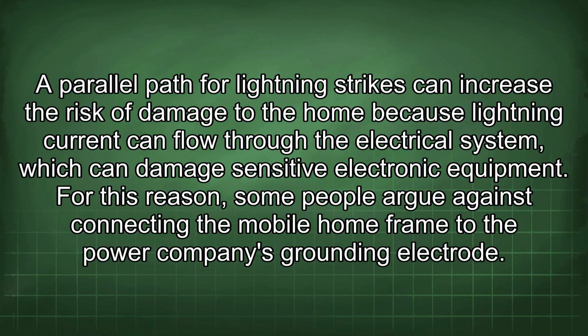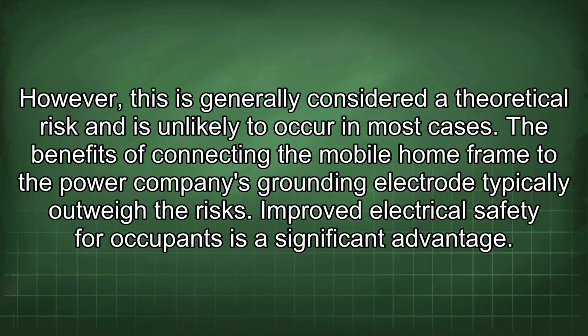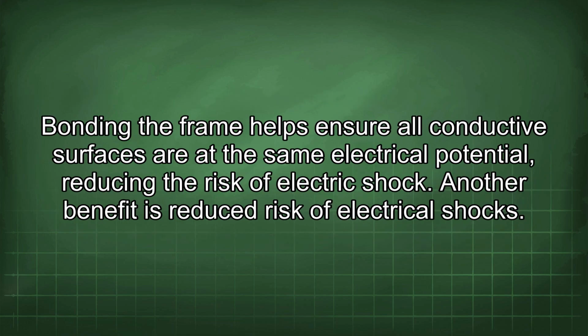For this reason, some people argue against connecting the mobile home frame to the power company's grounding electrode. However, this is generally considered a theoretical risk and is unlikely to occur in most cases. The benefits of connecting the mobile home frame to the power company's grounding electrode typically outweigh the risks. Improved electrical safety for occupants is a significant advantage. Bonding the frame helps ensure all conductive surfaces are at the same electrical potential, reducing the risk of electric shock.